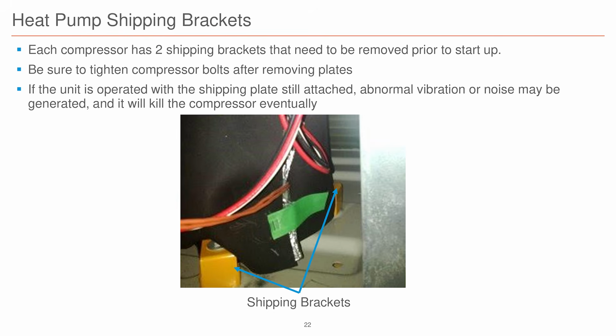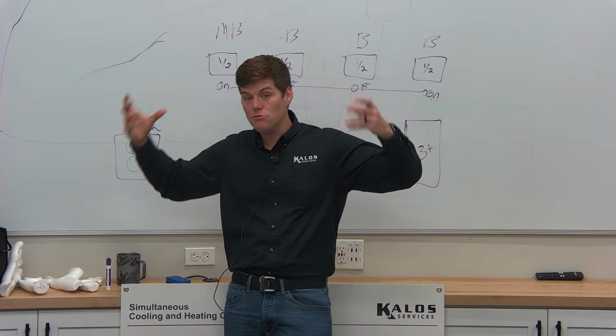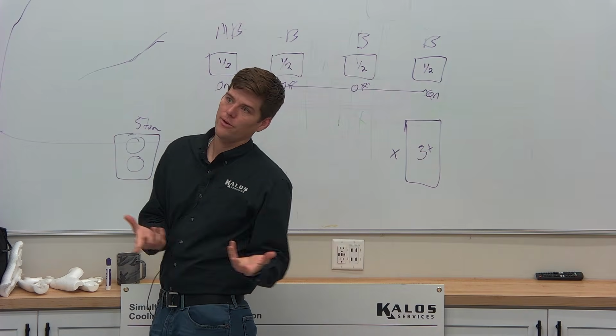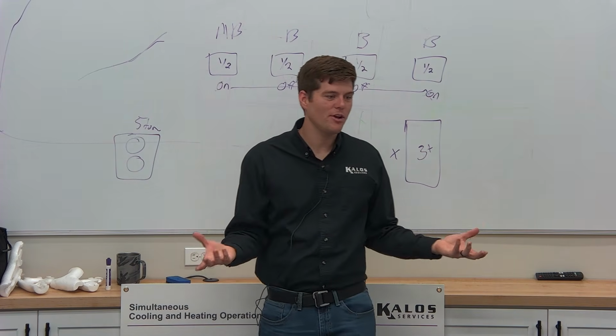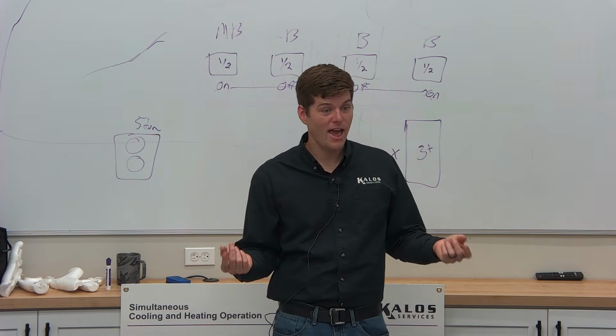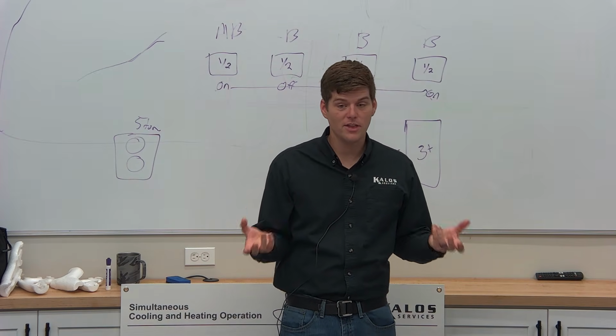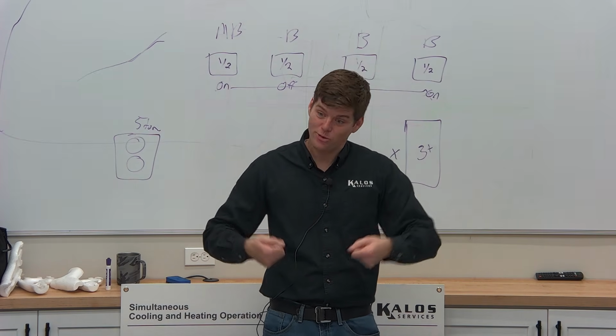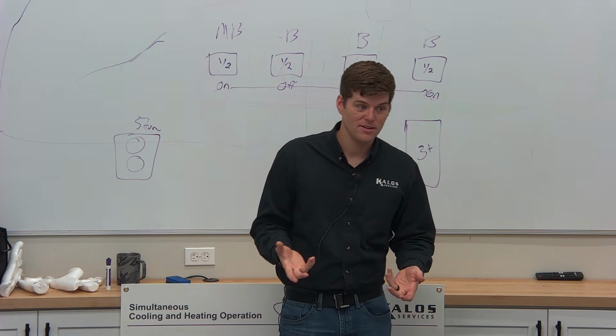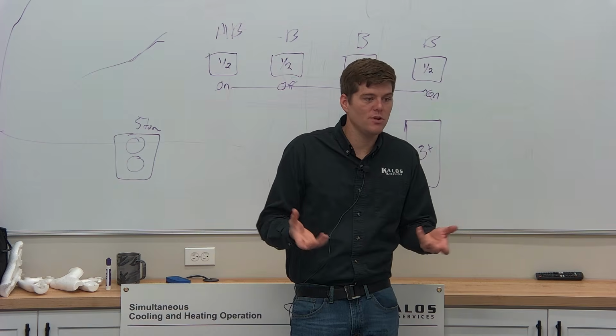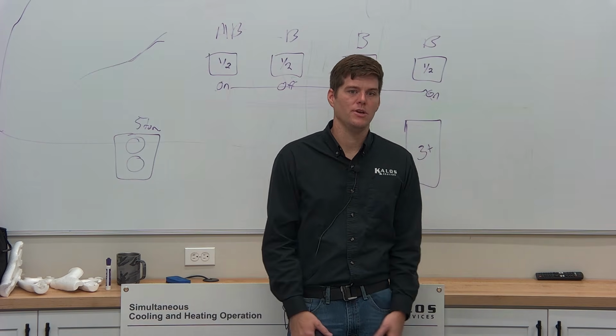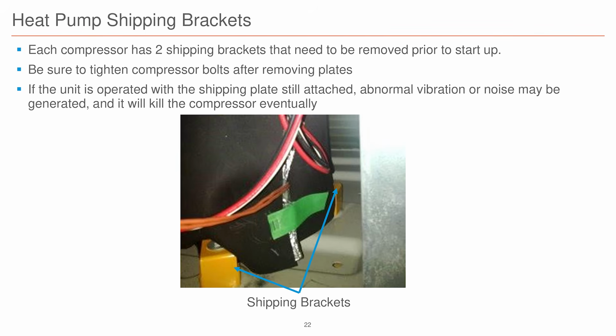Something to remember with these units: all these units typically come with brackets under the compressors from shipping. So when we think about an inverter compressor that has 168 different speeds, we think about what? When something is moving extremely fast, what does it do? It vibrates, creates very, very fast micro vibrations. Well, when you bolt it down to where it can't move, what happens? It causes damage. It can't move the way it's supposed to. So all these units come with shipping brackets to make sure the compressors don't clang around inside. You have to make sure you remove the shipping brackets under the compressor.